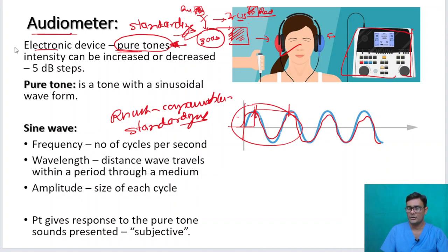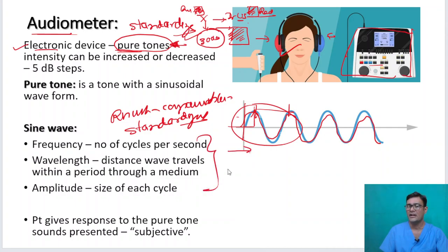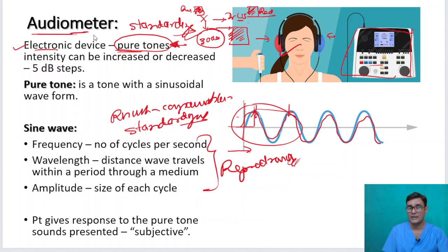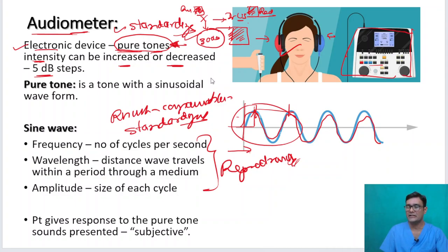An audiometer is an electronic device capable of producing pure tones with characteristics that are reproducible anywhere in the world. The key capability of an audiometer is that the pure tone's intensity can be increased or decreased in 5 decibel steps. We are essentially trying to test the threshold of hearing of the patient.